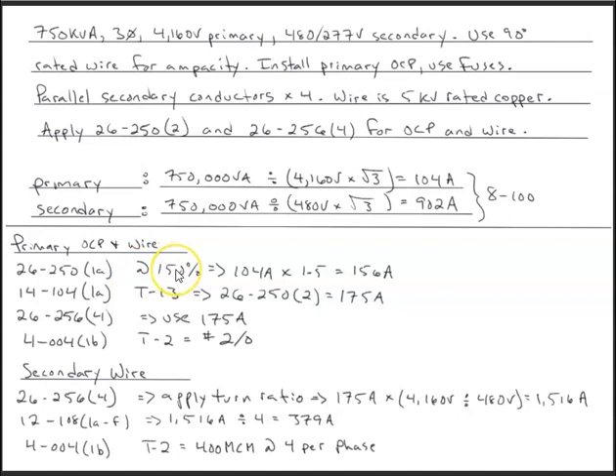So, and again, we're taking it at 150% according to the rule. We end up with this value, and 26250 is dealing with our overcurrent, right? This is not for wire. So the 156, we apply it into 14104, and 26250 subrule 2 is allowing us to go up to the next standard size. So we've been dealing with overcurrent devices using the language of maximum. Typically we would go down to the next breaker size, not up. In this case, though, we're going to apply this rule where it's allowing us to go to the next size overcurrent device, which is also stated under 14104.